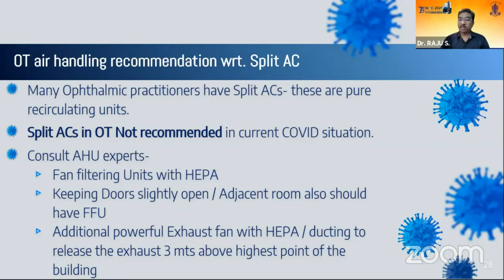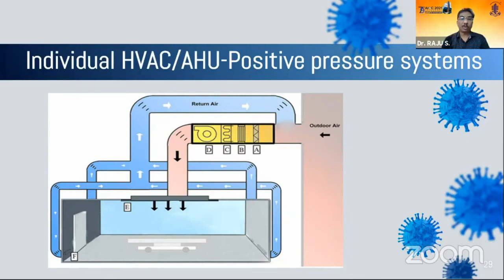An additional powerful exhaust fan with HEPA can also be used when you are using these split ACs. As far as the individual HVAC system or the AHU is concerned, these are positive pressure ventilation systems wherein you have a supply duct, then you have return ducts. The return air goes back to the system along with fresh air intake, and again the same air is supplied partly to the OT. So this is an example of an OT with AHU.